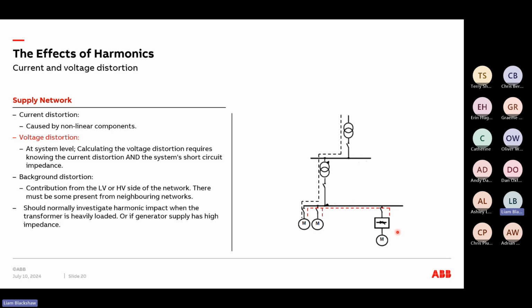But one thing we need to consider as well is things like background distortion. So things that are contributing from either the LV or HV side of the network depend on what we class as the point of common coupling, PCC. And that means whenever we look at harmonics, especially from a standards perspective, we always measure at the point of common coupling. In layman's terms, that means we always measure at the point where we're sharing our supply with another user. That could be on the LV side, it could be on the HV side. It all depends on the user's network.